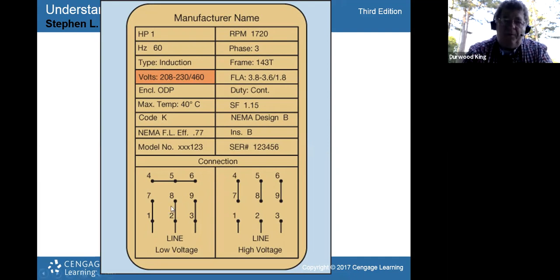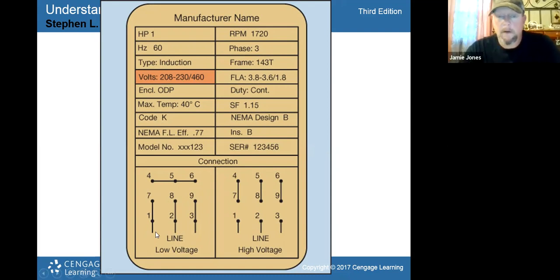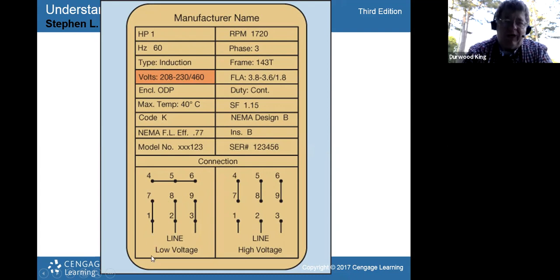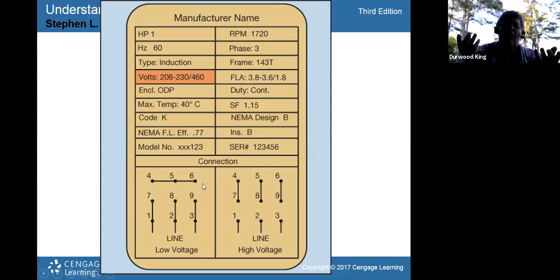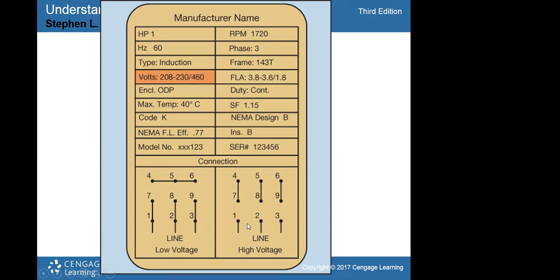So they're bound that they'll only run at 1 voltage, and there's not as much to wiring them. But with that wiring diagram there, can y'all see that? Yes, sir. So here you have your power line coming from your motor starter would feed into here, and it would connect with 1 and 7. So T1 off of the starter would join with 1 and 7. It would give you 3 wires together in a wire nut. Your line 2 off of the starter would go to 2 and 8. Line 3 goes to 3 and 9, and then 4, 5, and 6 will just go in the wire nut. Now, not many of you wired 480 in our shop, but we're going to go over that. And basically, that same motor could go 460, and it would actually run on 480. So the same motor, when you configure.